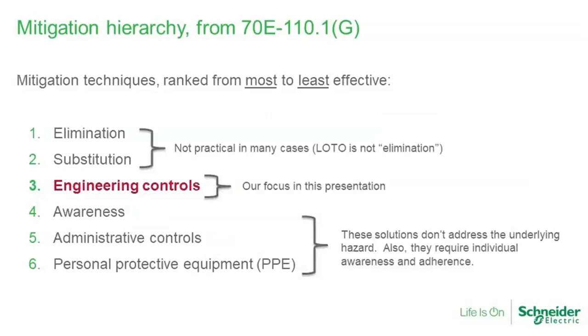NFPA 70E gives us another thing that can be useful. It gives us a mitigation hierarchy. It talks about different mitigation techniques ranked from the most to least effective, and starting right up there at the top, elimination. If we can eliminate a hazard, hey, we don't have to worry about it anymore. And I've got a note over there that says, not practical in many cases. Lockout tagout is not elimination. Certainly you can't eliminate electricity from a facility if you have electrical loads. I mean, we can't get around that.